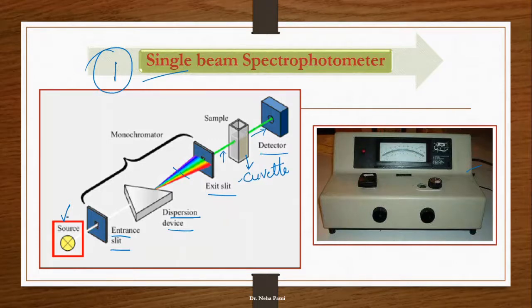The light which goes outside the cuvette could be transmitted light, and with the help of a detector you are going to find out how much light is getting transmitted, or basically what is the absorbance of this solution. The role of the exit slit is to allow one wavelength at a time, and then the detector will detect it. Single beam spectrophotometer has basic components: light source, entrance slit for monochromatic light, dispersion device to scatter light into different wavelengths, and the detector.